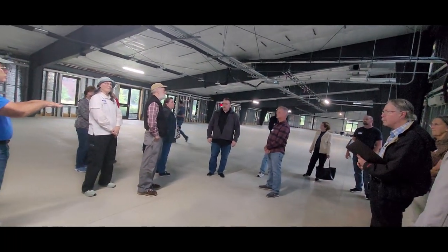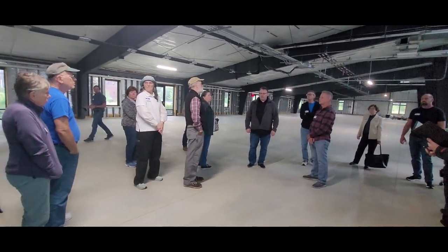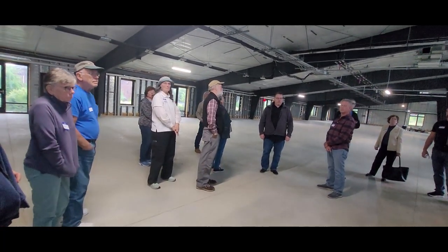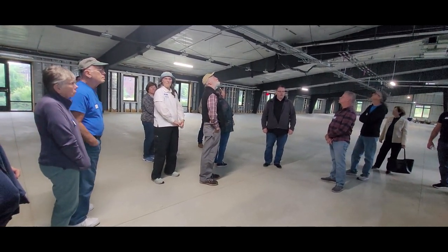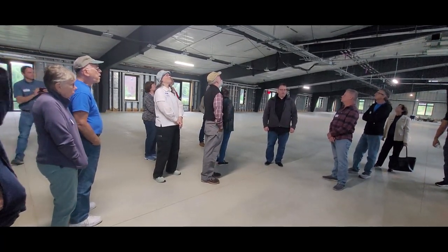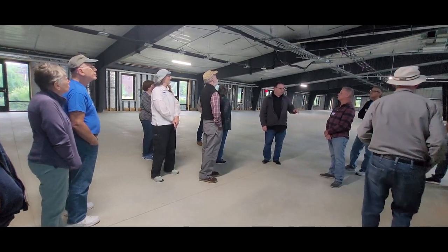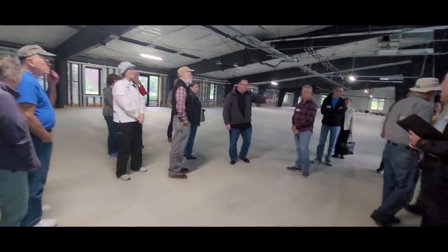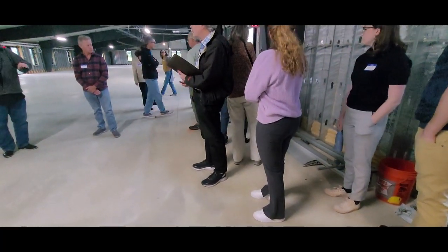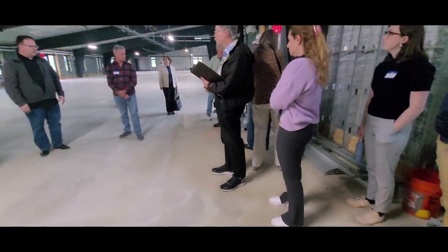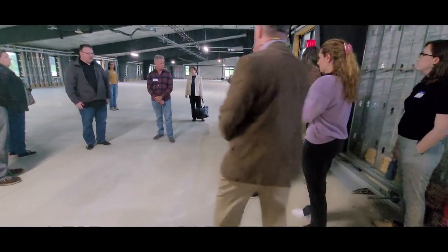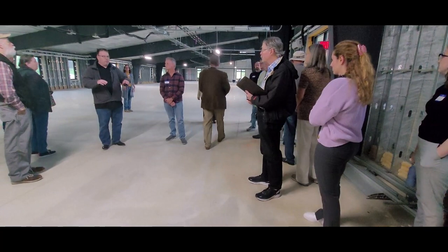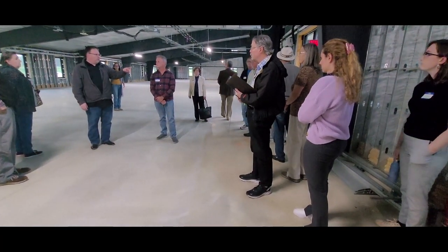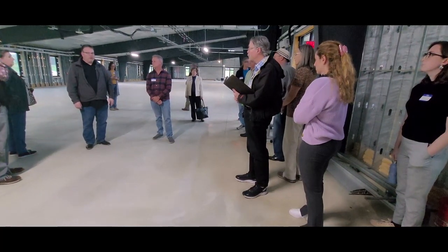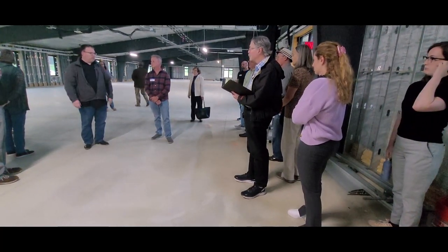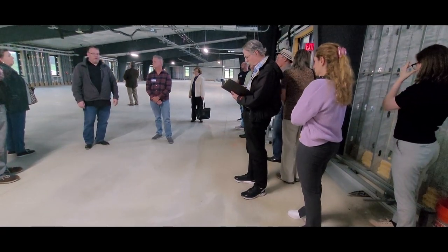How are you handling the bridging for the beams, same as you did on the wall? Same thing, yes. The ceiling beams, do you have an insulation layer on top of them? We have insulation on top of the ceiling beams. There is some leakage in the building around the bottom of the beams. We put a frost skirt in place, but just the way the building was designed, we weren't able to keep everything warm all the time. That was the weak point, the posts for the steel building. But there is a frost skirt around them to help minimize that heat transfer.